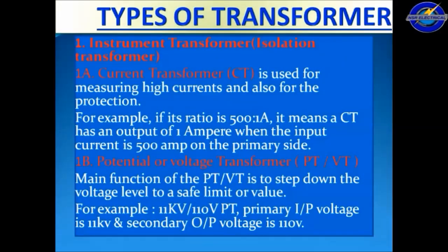Instrument transformers, also called isolation transformers. A current transformer (CT) is used for measuring high currents and also for protection purposes. For example, if the CT ratio is 500:1 A, it means the CT has an output of 1 ampere when the input current is 500 amps on the primary side.